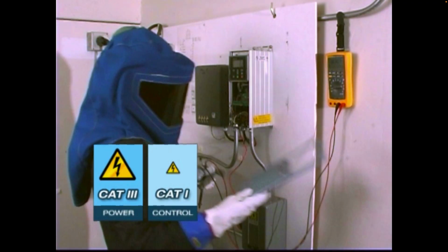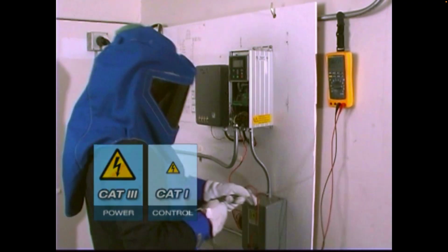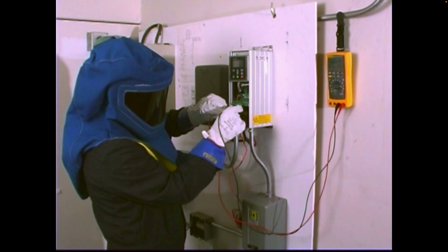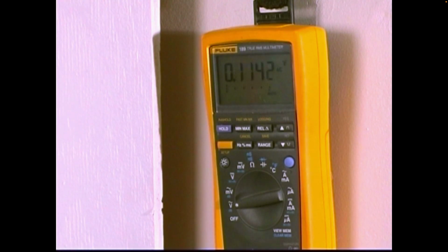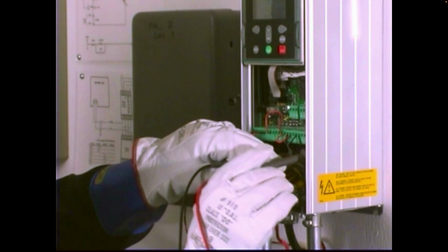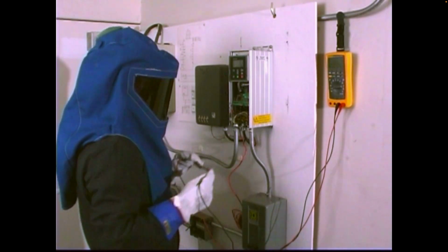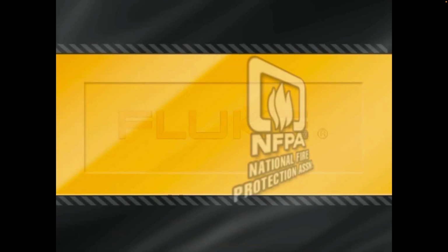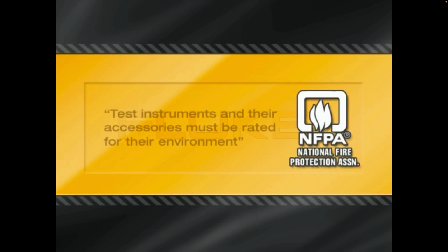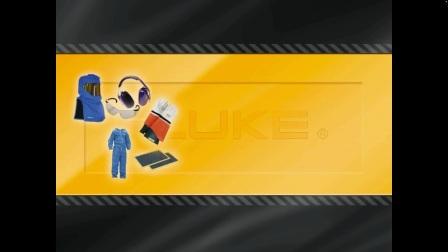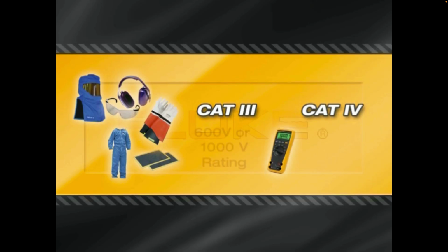In these environments, you should use the tools and personal protective equipment rated for the higher category. In general, where greater fault currents are available and as voltage transients increase, measurement becomes more hazardous. This is reflected by a higher CAT rating. National standards for workplace safety include test instruments as part of personal protective equipment. The National Fire Protection Association clearly states that test instruments and their accessories must be rated for the environment where they will be used. If you're working in areas that require personal protective equipment, you're probably in a CAT 3 or CAT 4 environment. You should be using test equipment rated 600 or 1000 volt CAT 3 or 600 volt CAT 4.